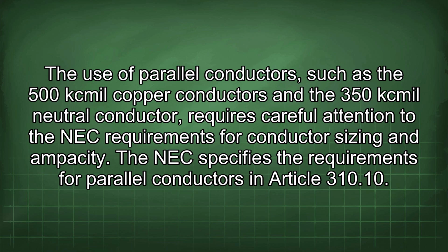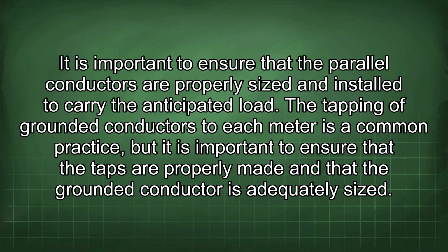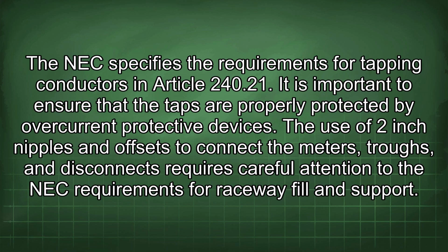conductor, requires careful attention to the NEC requirements for conductor sizing and ampacity. The NEC specifies the requirements for parallel conductors in Article 310.10. It is important to ensure that the parallel conductors are properly sized and installed to carry the anticipated load. The tapping of grounded conductors to each meter is a common practice, but it is important to ensure that the taps are properly made and that the grounded conductor is adequately sized. The NEC specifies the requirements for tapping conductors in Article 240.21. It is important to ensure that the taps are properly protected by overcurrent protective devices.